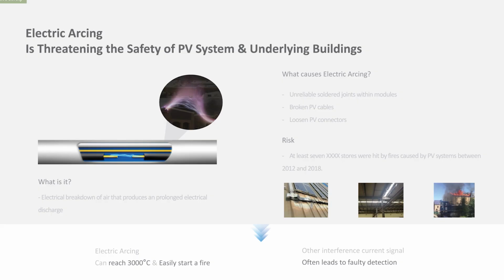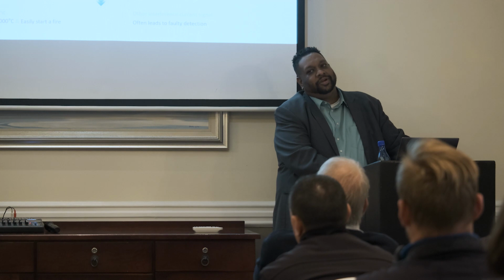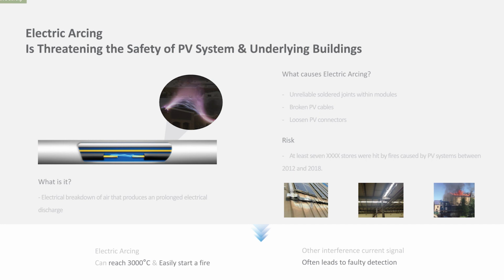Electric arcing is threatening the safety of PV systems and underlying buildings. Okay, so what causes electrical arcing? Unreliable solder joints on the PV modules, breaks in the cable, or loose PV connectors. This can happen in multiple ways, okay? There could be a defect in the solar panel. The broken cables could be from pulling cables. You kink the cable and it broke. And you also have loose PV connectors. The other thing we have in South Africa is rodents. Rodents chew on cables. They love cables. I'm not sure why. But they can also bite through the cables and create that kink in the cable.